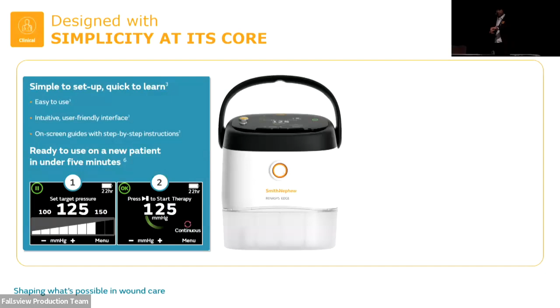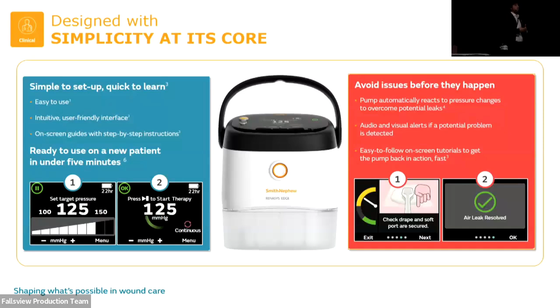It's not only about that. So if everything goes all right, fine, happy days. But what happens if there is some alarm, some issues happening on the pump that need troubleshooting? So we invented animated tutorials on board that will take you step by step through the troubleshooting process, whether it's a leakage alarm, a canister full, a blockage alarm, or you need to charge the pump, it will guide you step by step. And this is what I mean by keep it simple and simplify negative pressure.